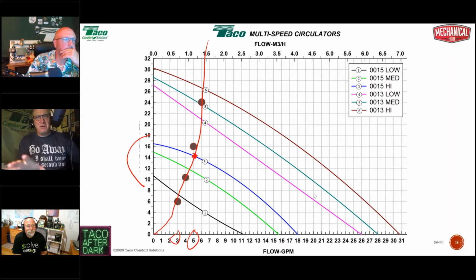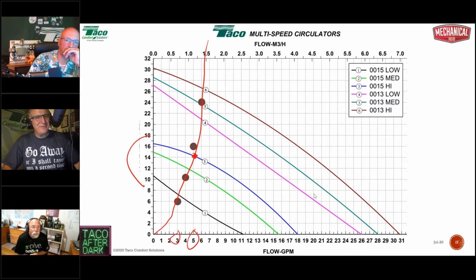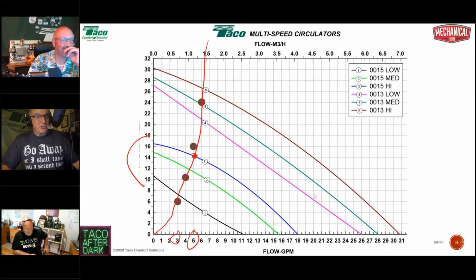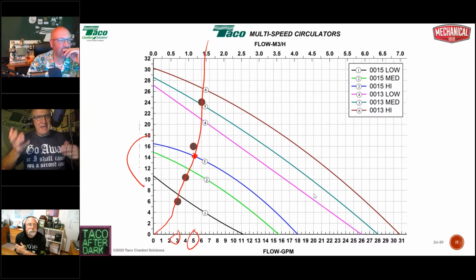People started putting these pumps in with zone valve systems, and you had steep pump curves, and they'd put them on speed 3 because, who knew? I've got zone valves, that's a lot, I've got to go to speed 3. And what would happen? They'd bang like hell. Then you call up and say, this pump I'm putting in, I don't know what's going on. I've got it on a zone valve job, and these zone valves are banging like hell. Well, what's the response? Why didn't you put in a pressure differential bypass valve? Didn't you know you were supposed to? And very quickly, that became the common installation method.